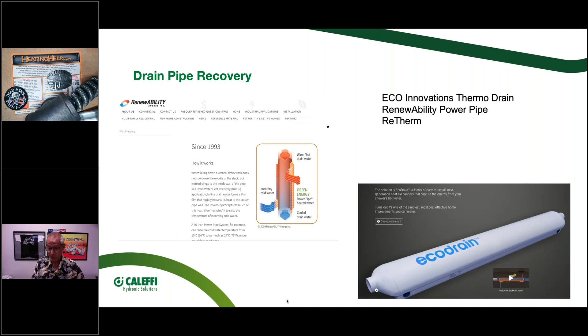Yeah, so what it's going to come down to is you start going with higher flow rates, it's going to cost you more pumping power. So that has to come in. Now, certainly for these little residential applications, that's probably not going to be a deal breaker. You're not going to get out of the typical little wet rotor size pump. But if you're doing a large application, I'll show you one that I visited a while ago, that can make a huge difference if you're starting to run 20, 30 horsepower pumps to run all this. You want to pay attention to that. So let me get back to this one here.